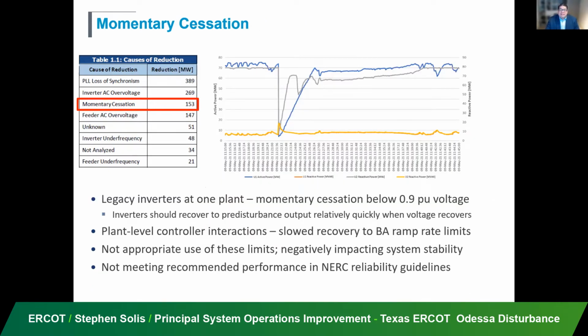We did have some legacy, older solar PV plants that experience momentary cessation. Our rules don't allow that anymore. And most of the solar OEM manufacturers understand that and design their equipment so that there's not momentary cessation. But we did have one facility in particular that went into momentary cessation. But you'll notice that the recovery time is still hindered.